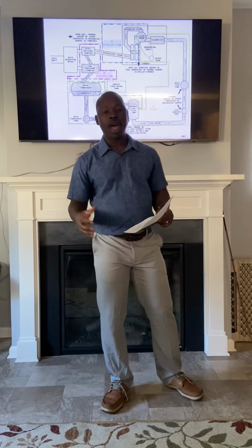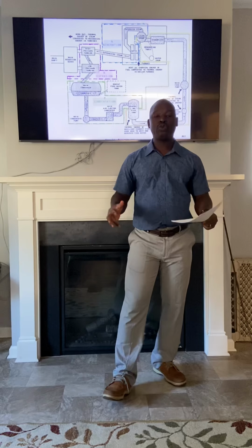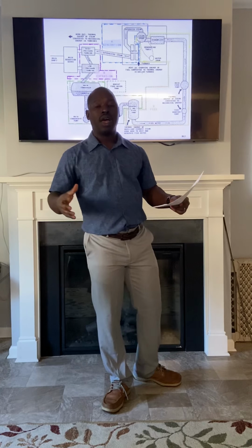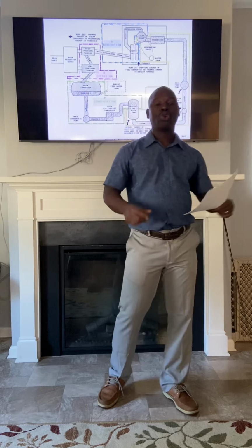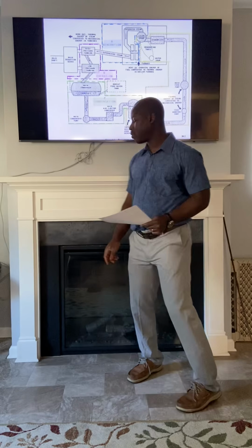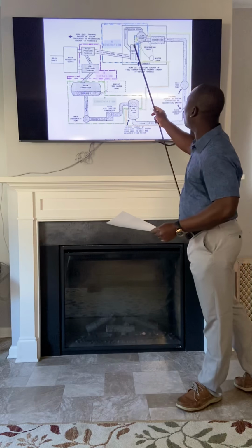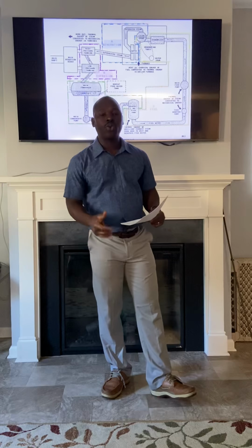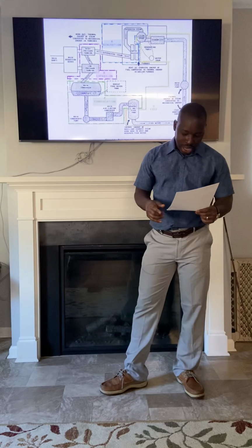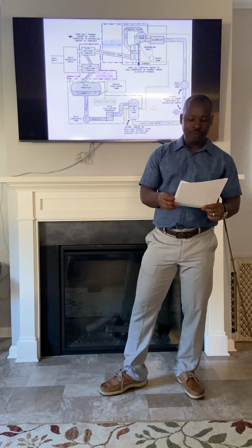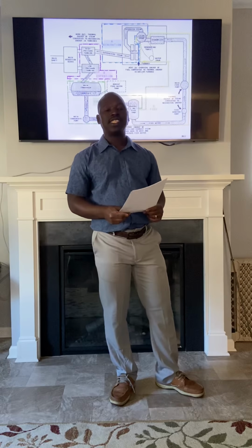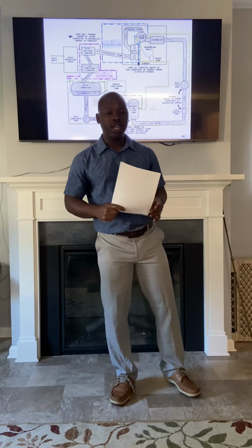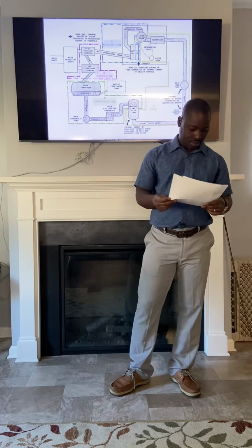As feed water travels back up into the tubes surrounding the furnace, it gets heated up and vaporized into steam and rises back up into the steam drum, where all droplets and moisture are removed from the steam by the cyclone separators. The steam continues its path to the superheater, which is located right here. The superheater will increase the steam temperature to 850 to 950 degrees Fahrenheit. Then steam exits the boiler through piping ready to be used by the turbines.